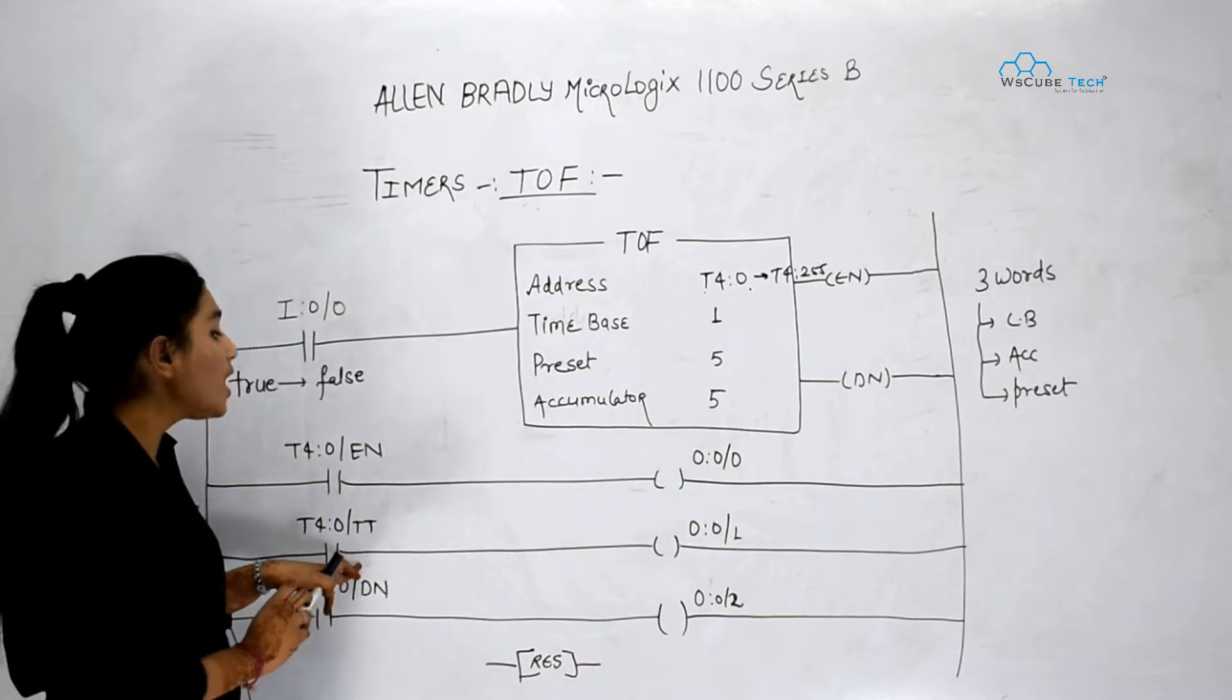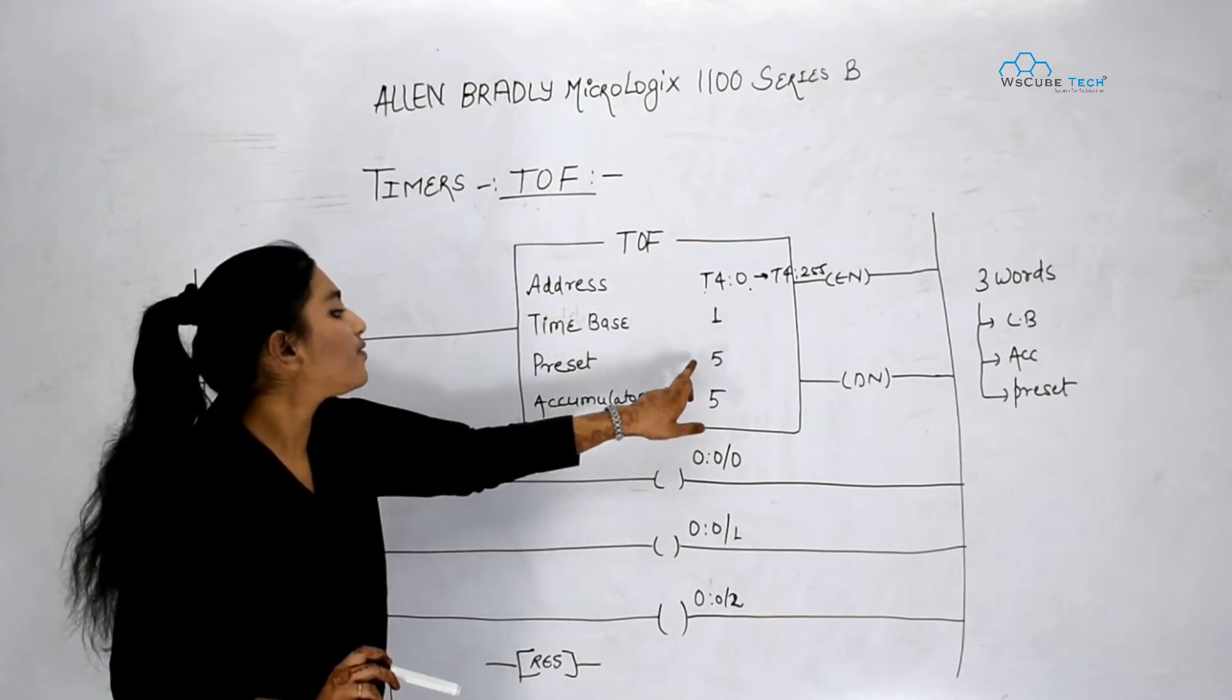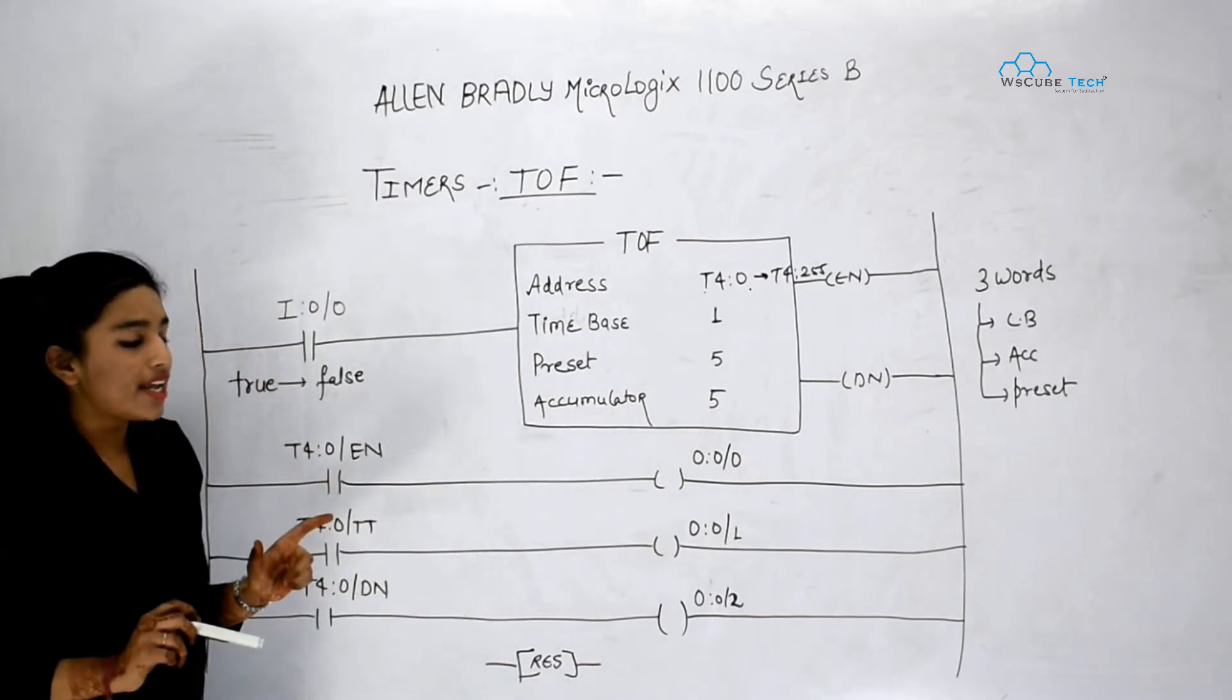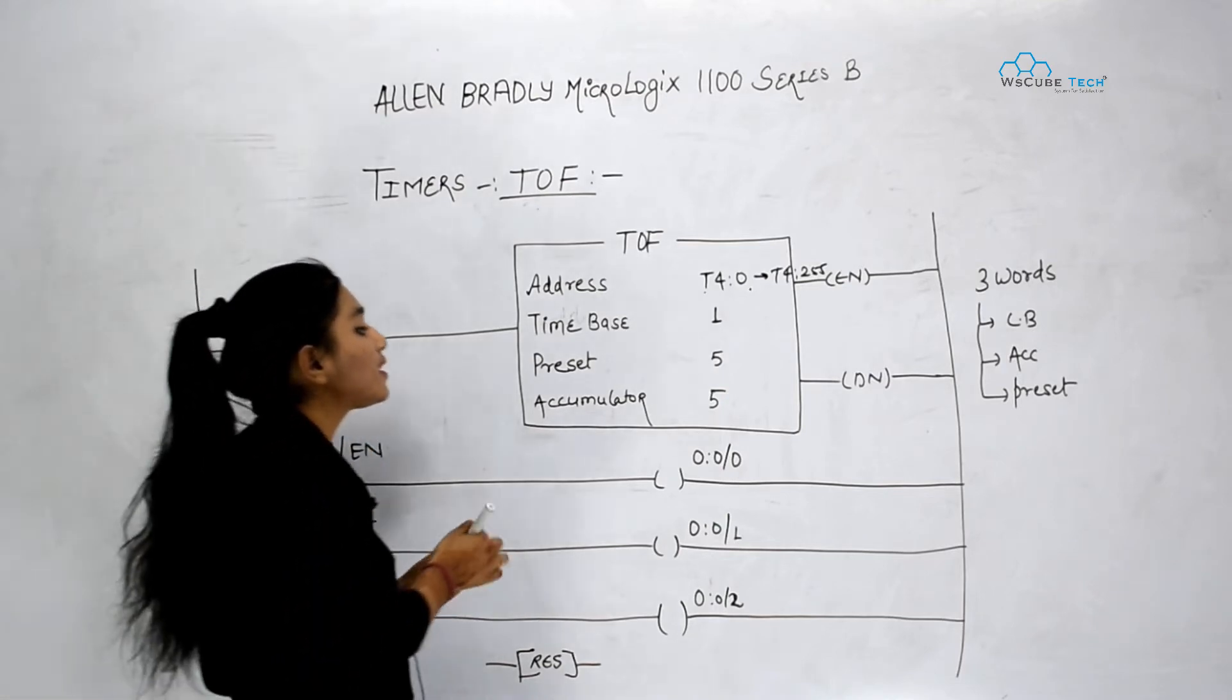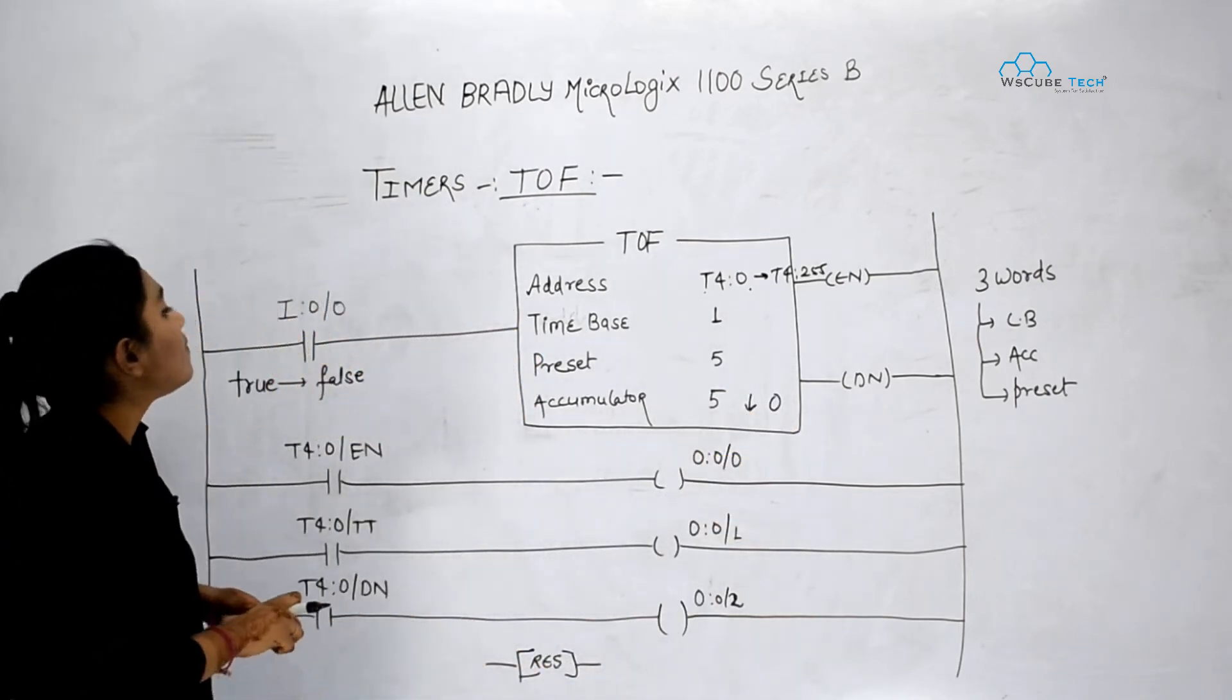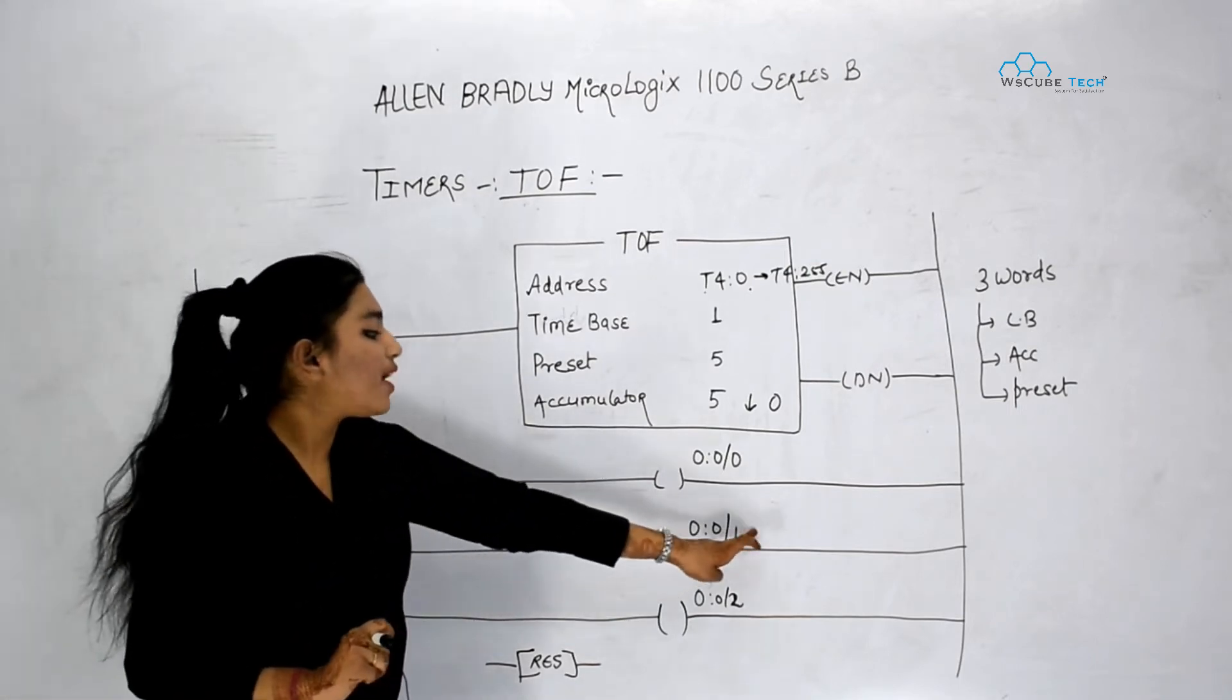Next we have got TT bit. In TT bit when my accumulator value is not equal to preset, it means right now we have written 5 in our preset and 5 here also. So when my rung becomes true to false, when my rung becomes true to false that time only my accumulator's value will start decreasing and it will attain 0 value. So when accumulator value is not equal to preset it means it is decreasing, that time TT bit will be 1 and my output will be there.